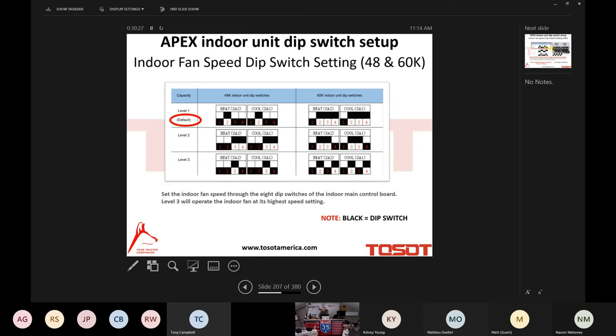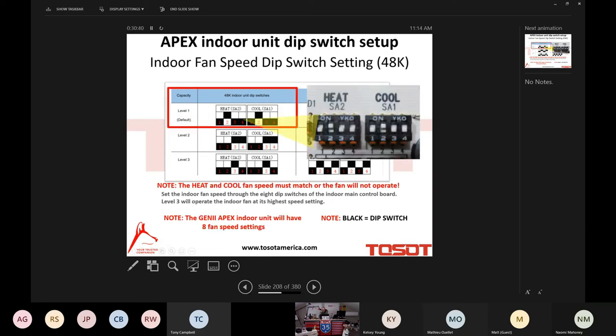Well, I made a note at the bottom of every slide, and it says the black is the dip switch. That's the position of the dip switch. So dip switch position, right? That's what I want to show you here. And this is exactly what I'm talking about. Here we have level one for the 48,000 BTU indoor unit. Again, that's what I have here in the house. And for level one, you'll notice that the number two dip switch is in the on position, right? That's the one that is lifted, if you will. Does that make sense, guys? So always know that the dip switch is the black square. I think that's the best way to look at it until we figure out an easier way to look at it and to demonstrate it.